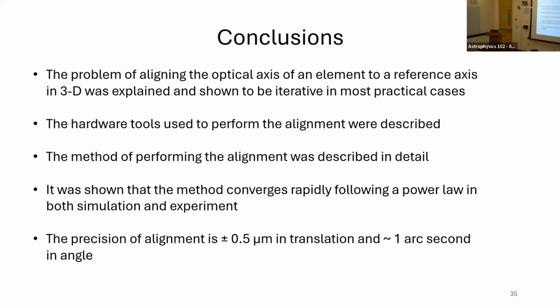Yeah, what if the lens has a little bit of astigmatism? Let's start with that. Well, this is one thing I didn't talk about: because we send out essentially a perfect wavefront, I would guess 20th wave or so, if you've got as much as a tenth of a wave, you could see it in the symmetry of the return spot. I see, you say you literally can't align better than that anyway.